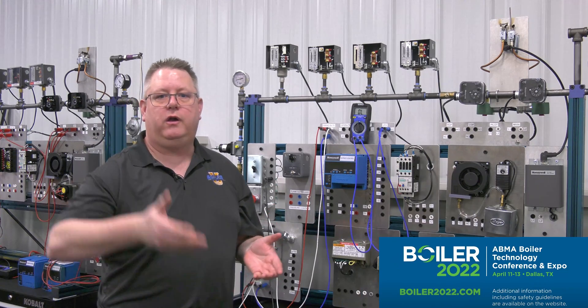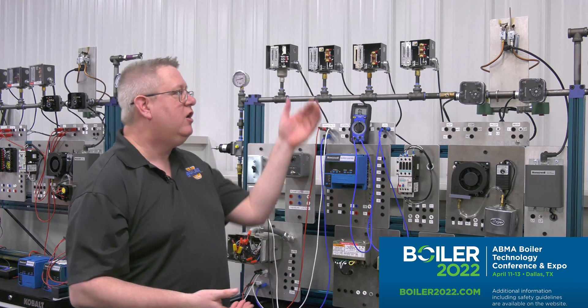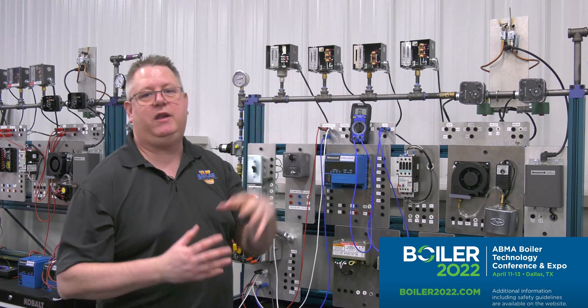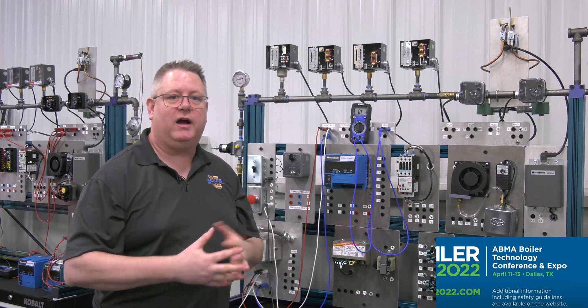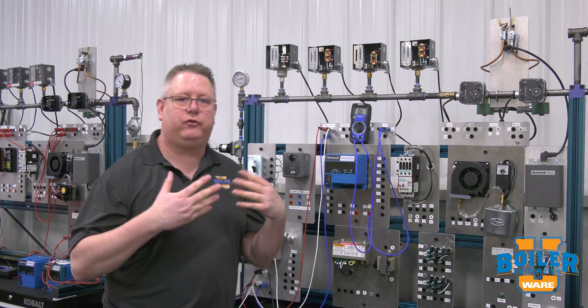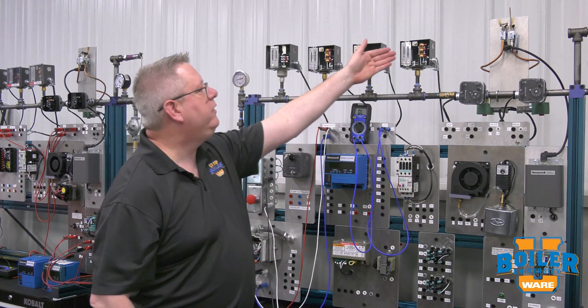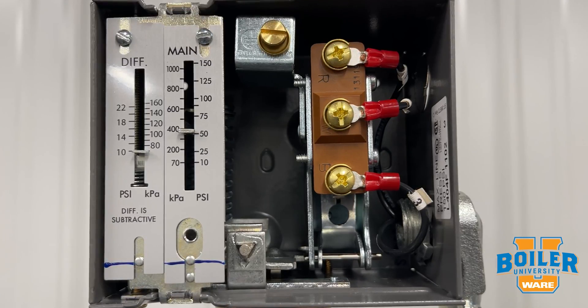Walking the firing rate up slowly as required, but it is necessary in many cases if we have boilers that start automatically by time clocks and things like that, because it will reduce the impact of thermal stress on the boiler. This switch we are hoping to prove that we have pressure to allow us to run.